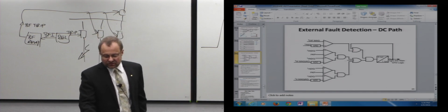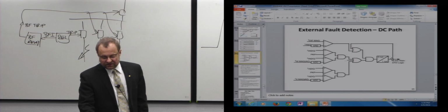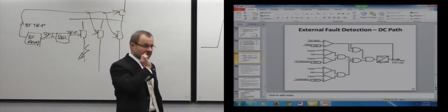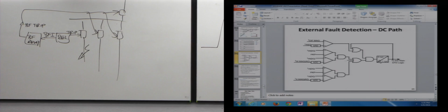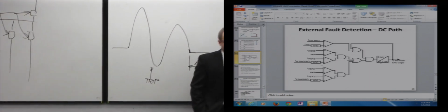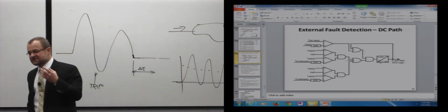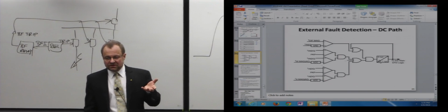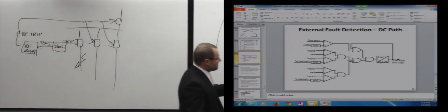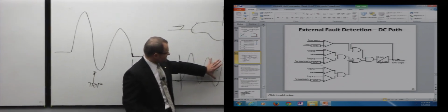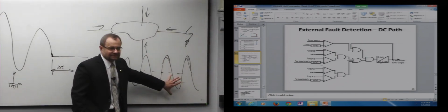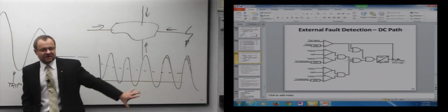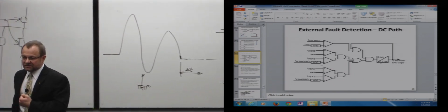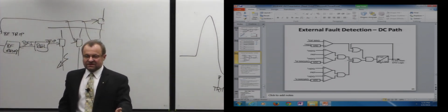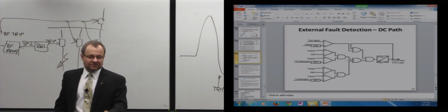Now, there is a sealing loop here. When I declare external fault, I will maintain that declaration this way. Why is that? Because that DC will disappear. One result of CTs not liking a DC component is that they will not pass it through. So when the CT saturates, the waveform will center itself. I mean, CTs will not pass direct current, so that direct current will disappear on me. So if I am looking at the direct current, that logic will drop out, which I don't want.